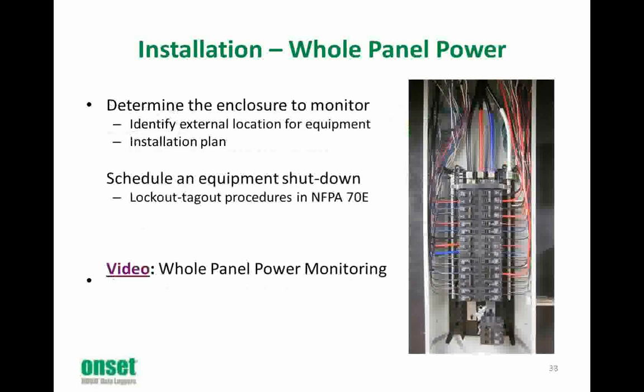Once we determine the enclosure to monitor, we will look at the desired location for our equipment and come up with an installation plan. Because this is a permanent installation, we will want to de-energize the equipment. It may be necessary to schedule this process with a facility manager to ensure all parties are aware of the interruption of power. Once this is done and we are ready to move forward, we will shut down the equipment and follow the lockout-tagout process as described in the 2012 edition of NFPA 70E. The following video will go through the installation process.